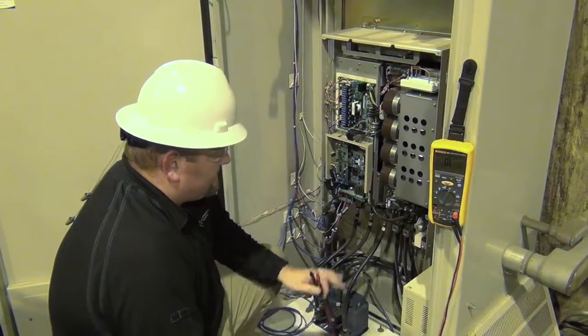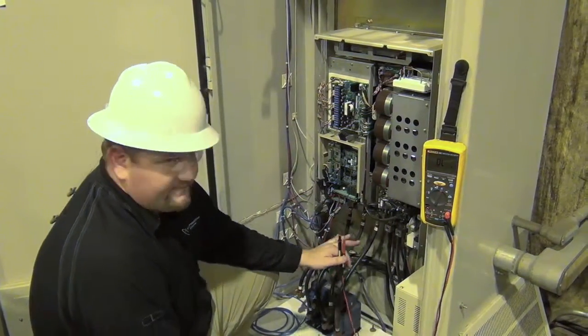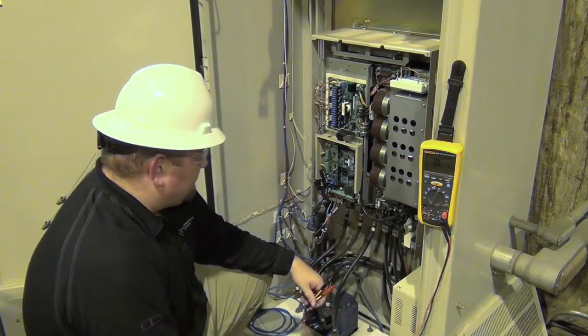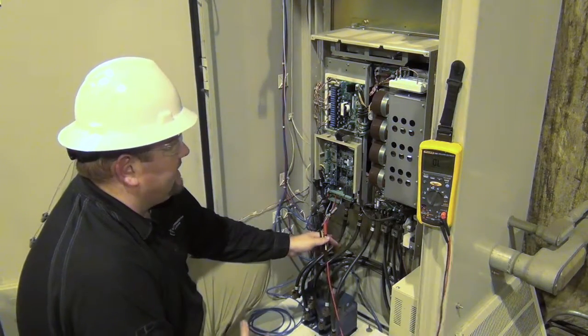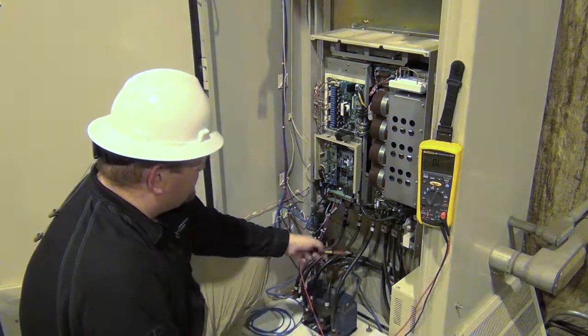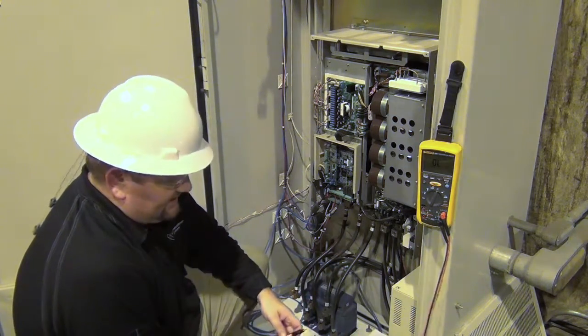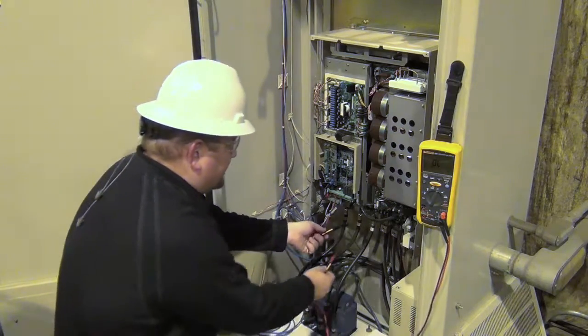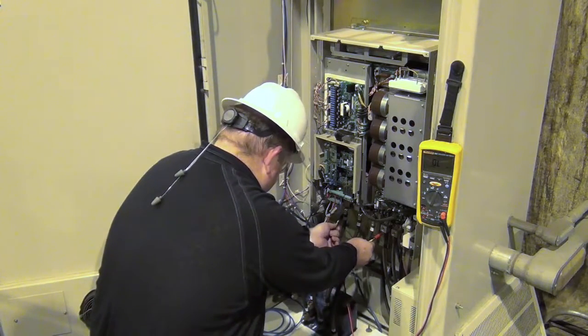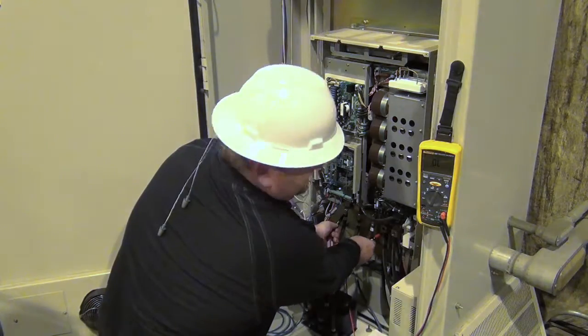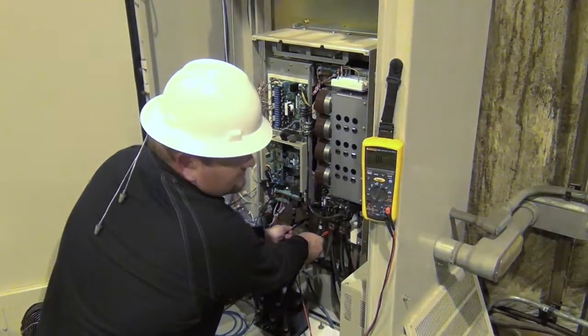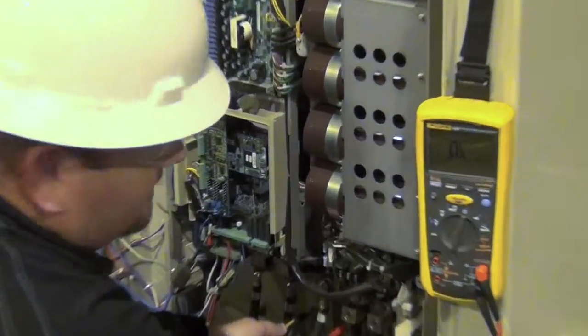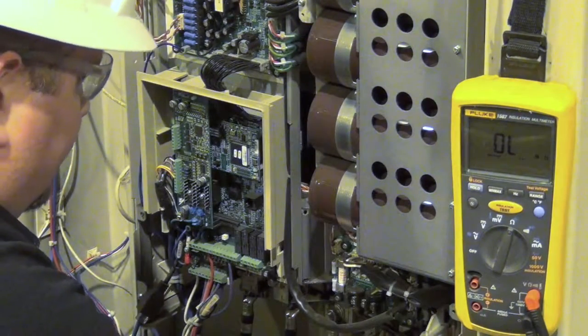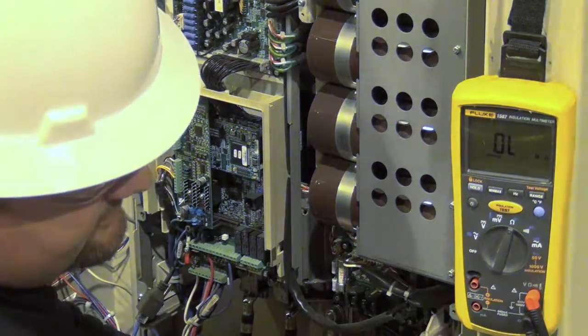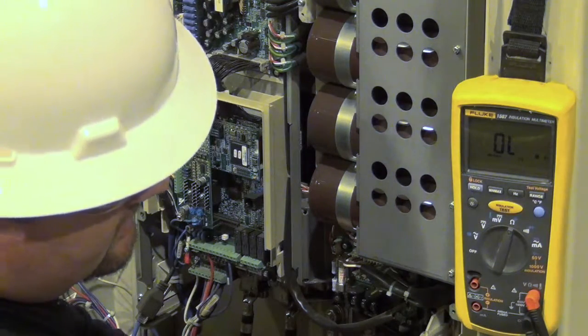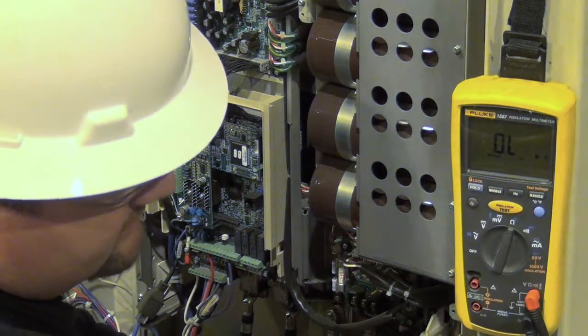Okay, so now that we have verified our control circuit and we verified our input and our output section, the last check we're going to do before we get into the cleaning portion of the maintenance is just do a line to ground check on the inputs and the outputs. So it's a simple resistance check, looking for an abnormal reading to ground. So we got a good no connection there, no connection there, no connection there, and we'll do the same to the output section. Nothing, nothing, nothing.